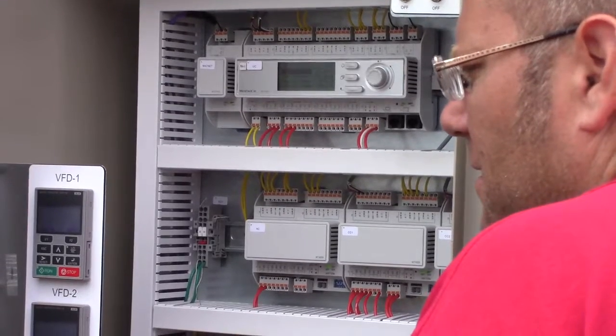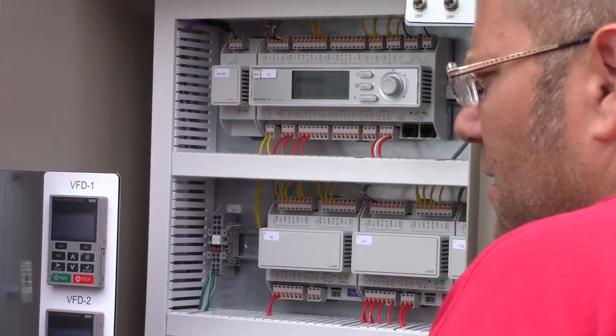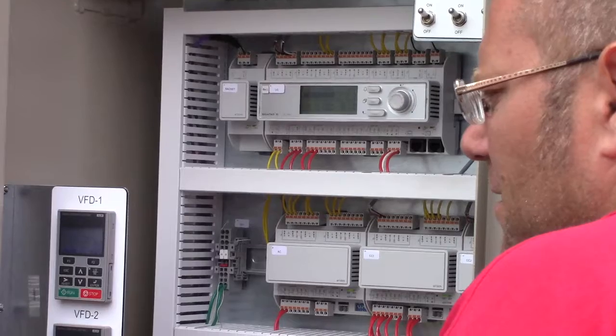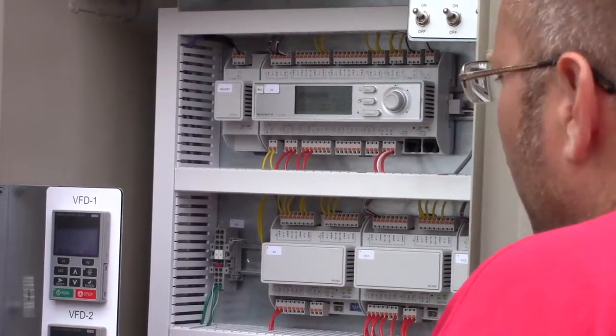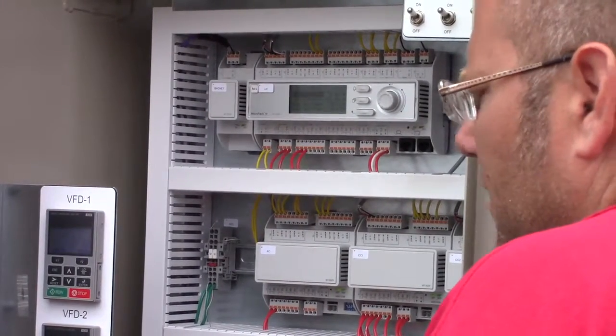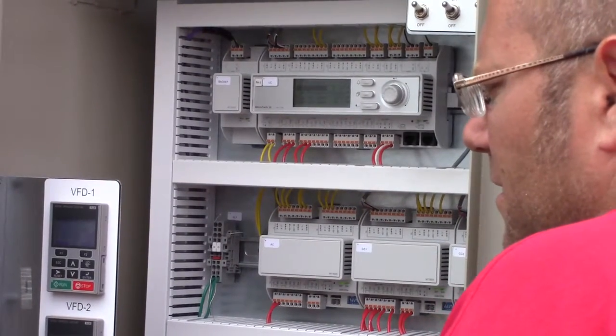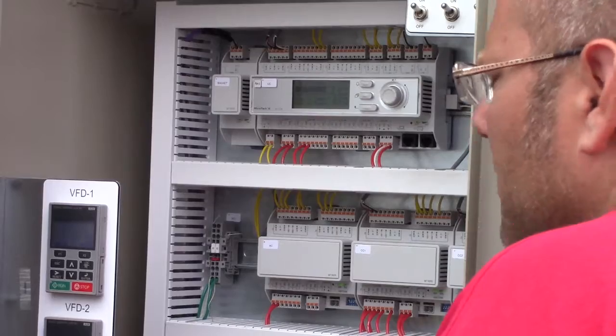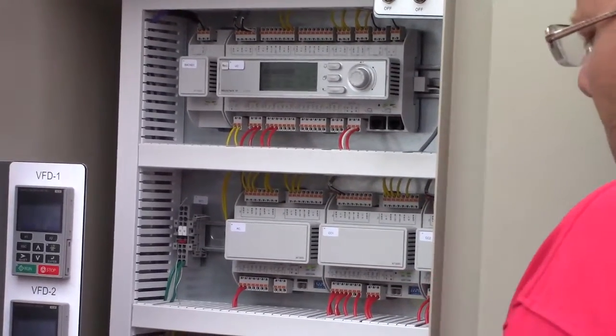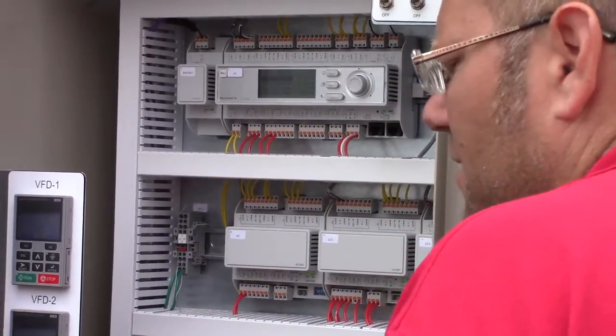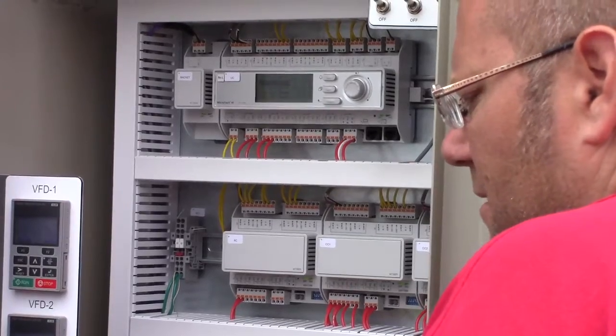And if you look at the capacity of that valve, if you're doing 20 and the target's 15 and you're at 100%, you're probably a little light on gas. Right. You can kind of guesstimate that information just by looking at where the valve actually is. If you're at 50% and you're at 15, the target might be 15, you might be right on point. So the nice thing about that is you can get a better idea where your charge is because you know what the valve's being told to do.